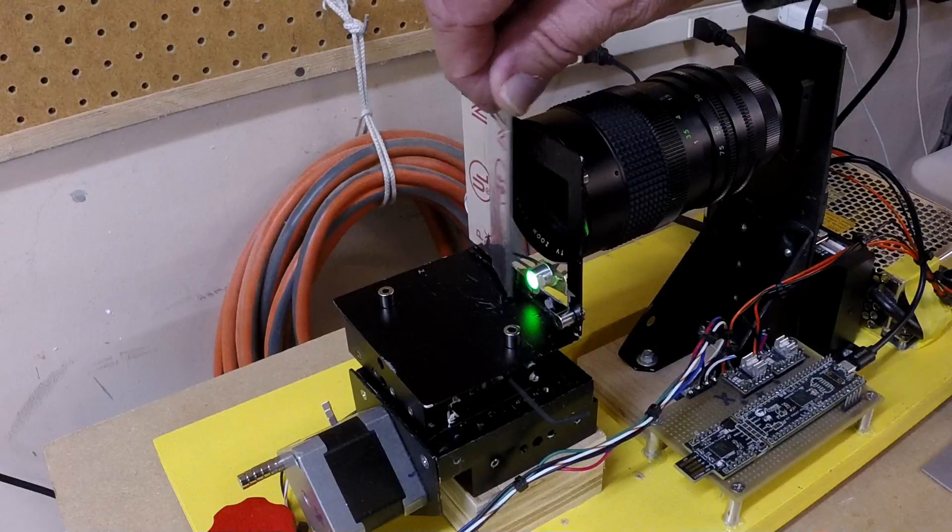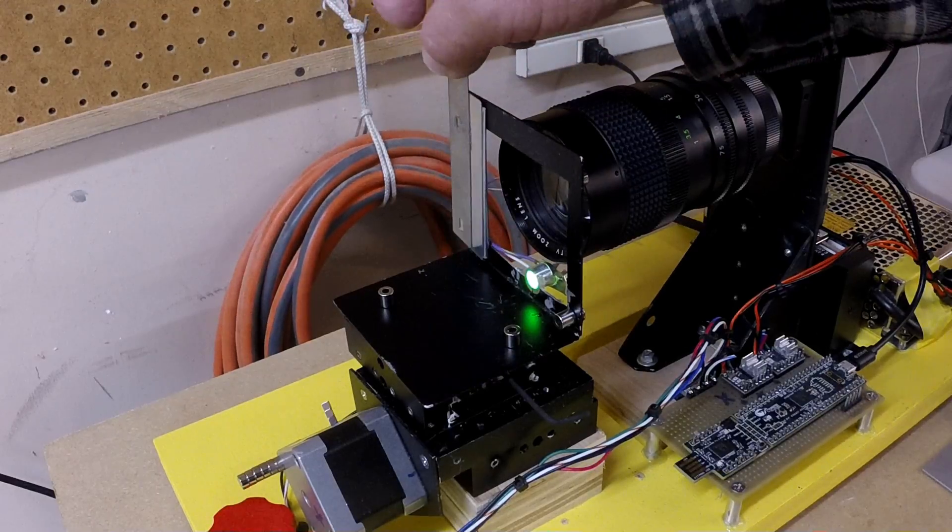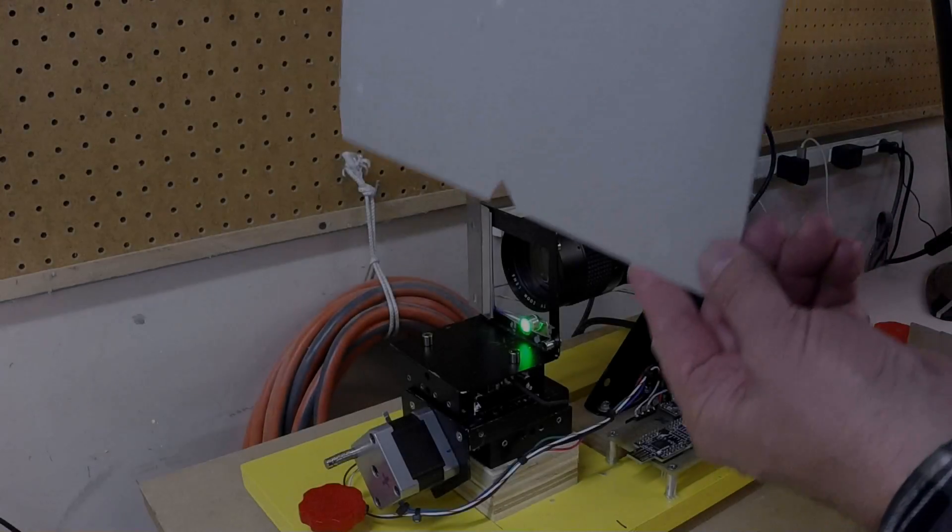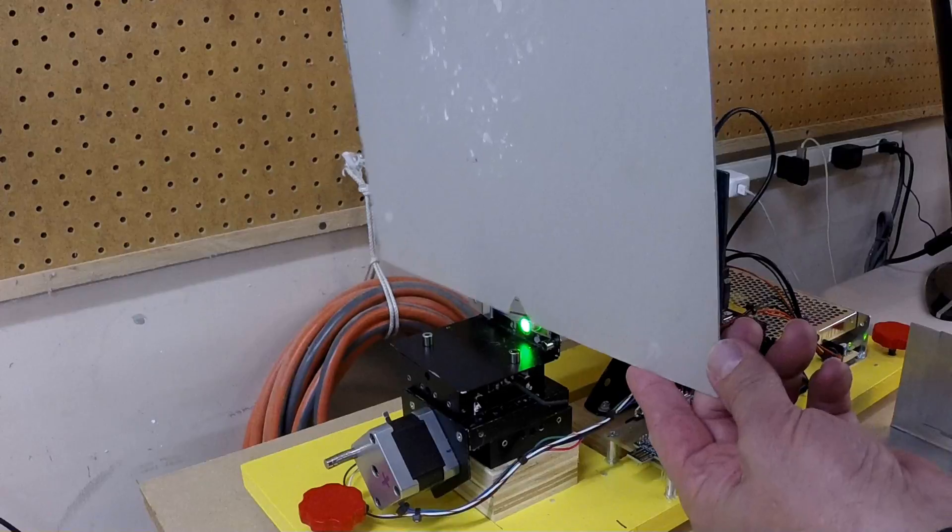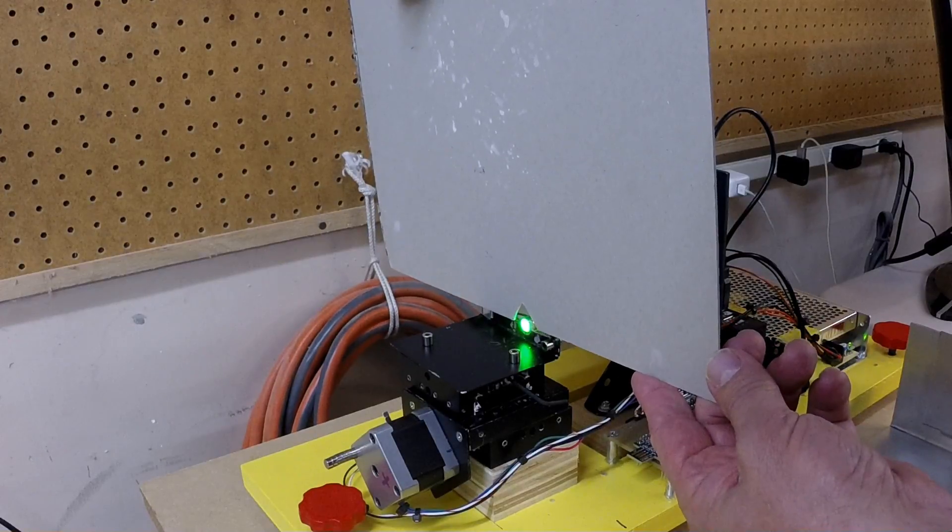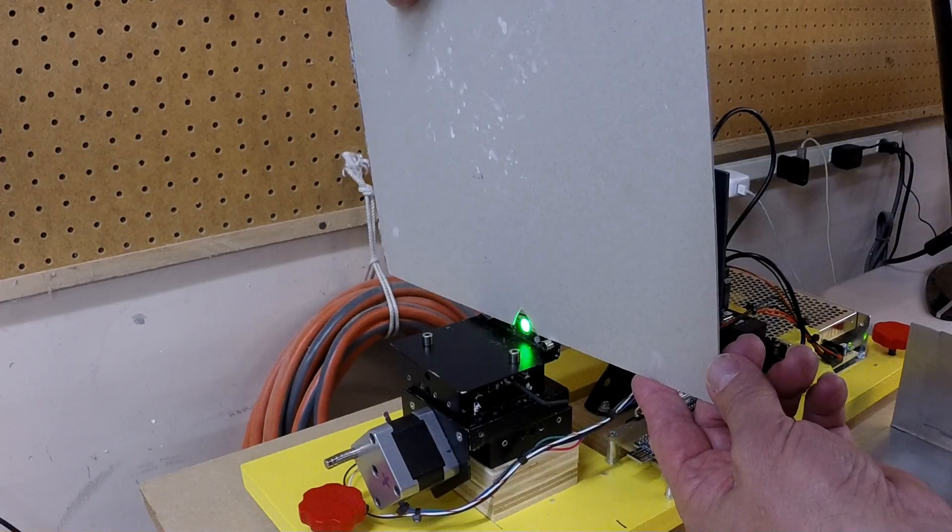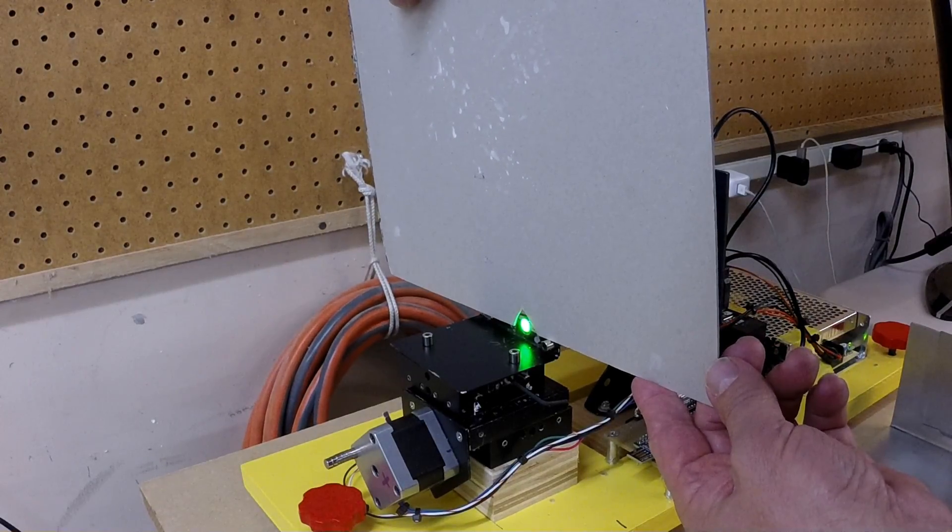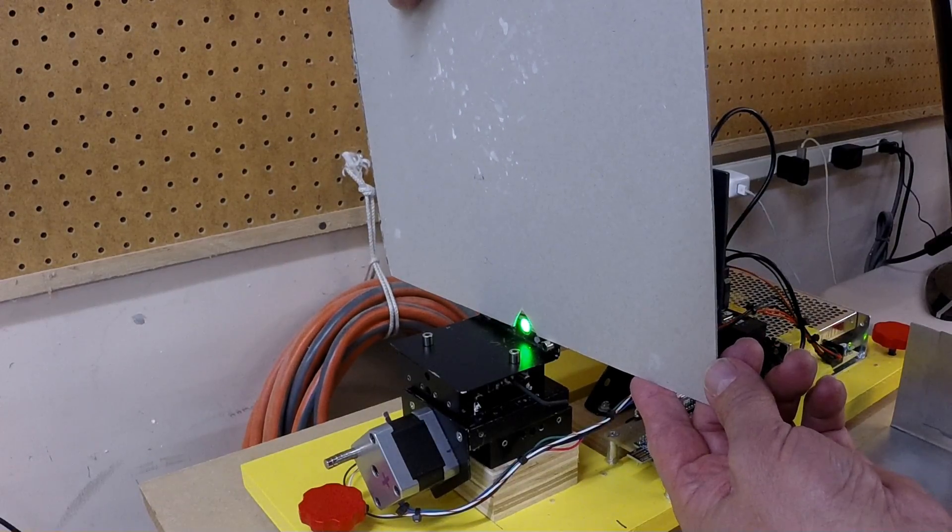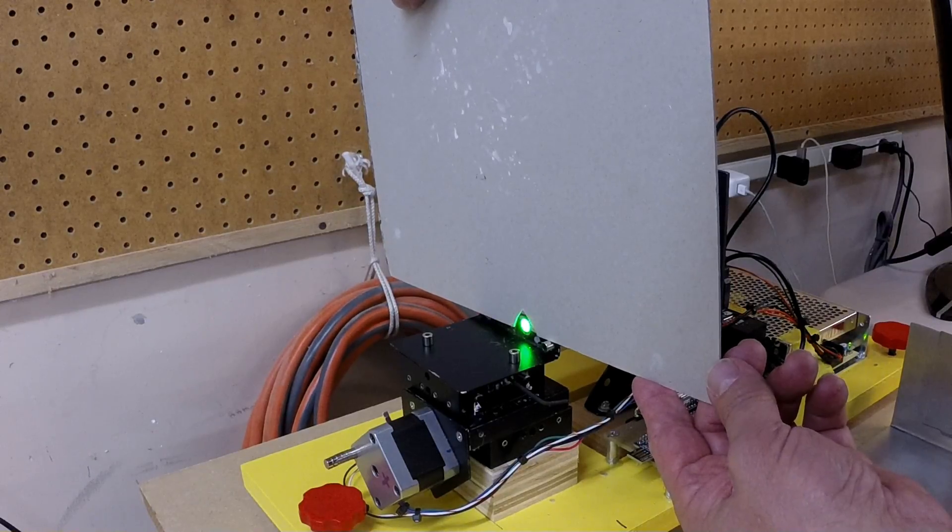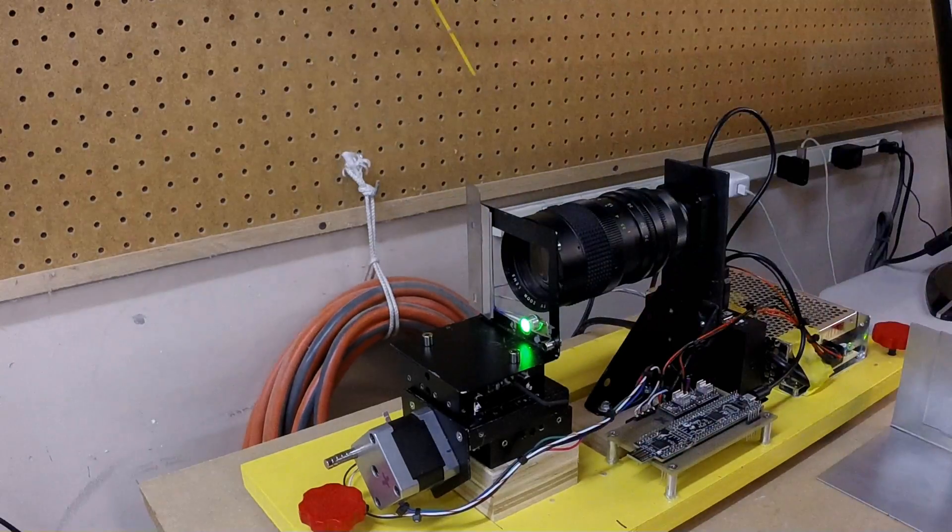I then darken the room, turn up the LED brightness as far as I can get it, and then I use a piece of cardboard to observe the reflected image off the mirror back to the tester. I can use this to get a rough position of where the tester needs to be.